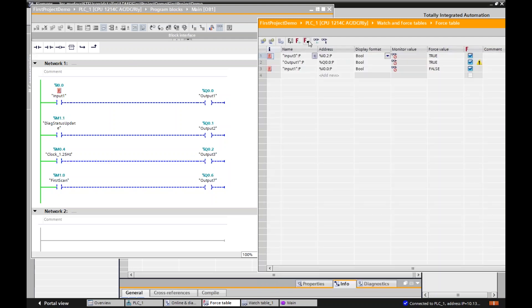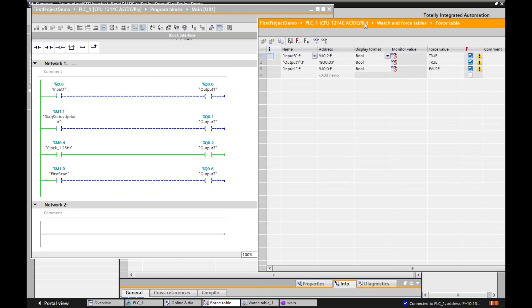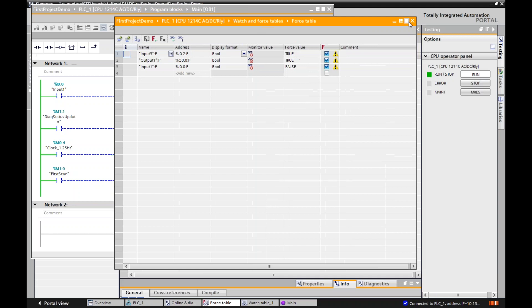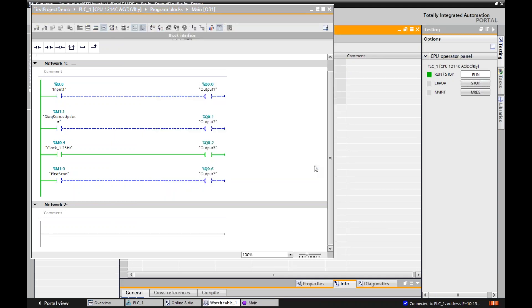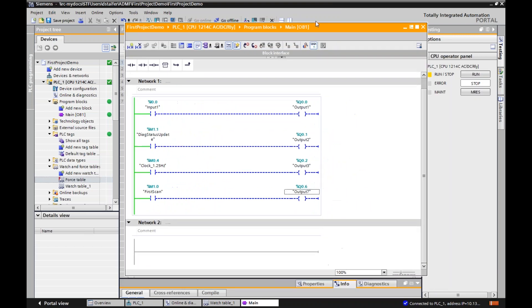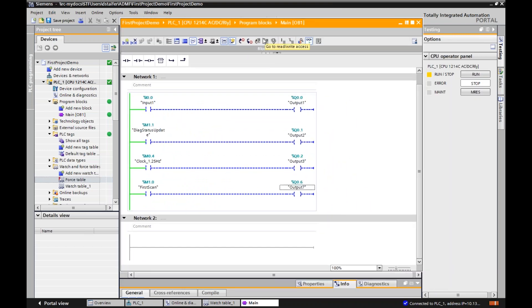To stop all this, I just go up here, stop all forces, and remove that. Now it's important — I found this out the hard way — make sure that you stop your forces or it won't allow you to make changes until you do. I was doing this PLC in another program, forgot to take forces off, and moved it from a lab to my office. I had to go online and remove the forces in the controller before I could download my new program. But that is clock bits, system bits, watch tables, and force tables. Thank you for your time and I hope you have a good day. Sorry if this wasn't my best video — doing this in my office during the day, I get interrupted sometimes.